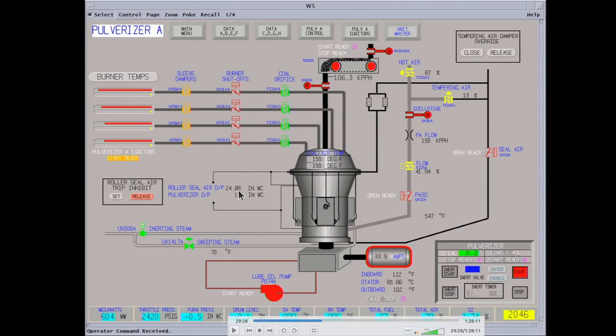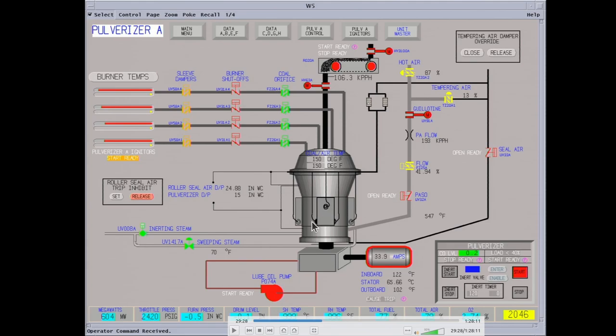The key on these pulverizers is the DP. If you get high DP above 30 or it starts climbing, you know you're plugging up — coal is building up and isn't going anywhere. At that point you either have to increase the air and shut the coal down to try and get it cleaned out. All the bearings and moving parts have seal air on them — tempering air is fed in to keep coal dust out of all the bearings on the rollers and all the moving parts on the pulverizer.